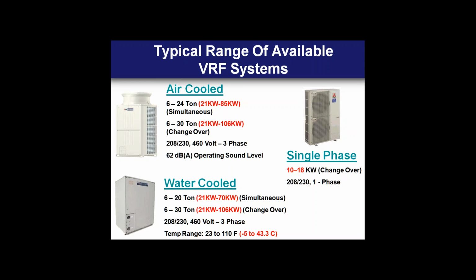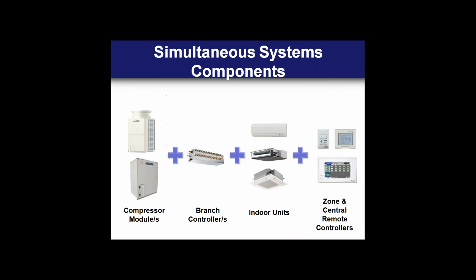What's also important to note about those is their wide temperature range. Typically they have ratings between 23 and up to 110 degree condenser water inlet, so perfectly well suited for geothermal applications. There's also a single phase line that most manufacturers carry that's going to be in the 10 to 18 kW range. That is strictly a changeover line. So one thing I didn't mention is most manufacturers have 2 variations. They have a changeover system where all the zones have to be in the same mode at any given time. And then they have a heat recovery system variation that allows simultaneous operation with heat recovery. On the single phase equipment, that's not available typically. You're just dealing with changeover.